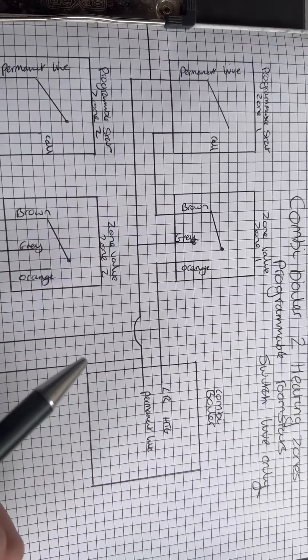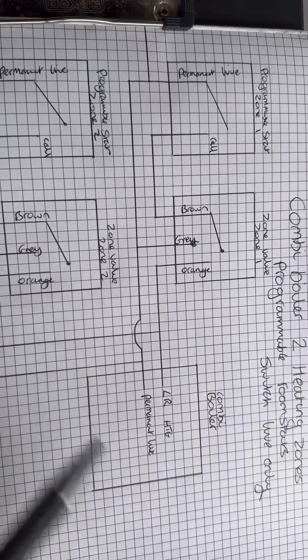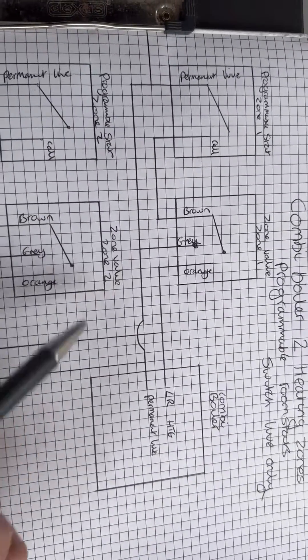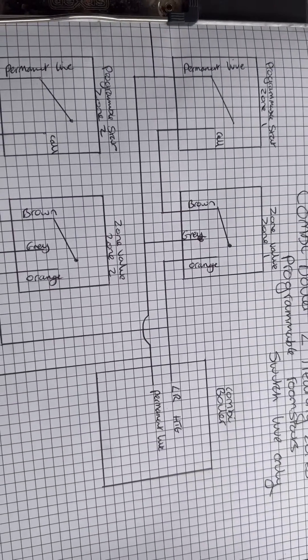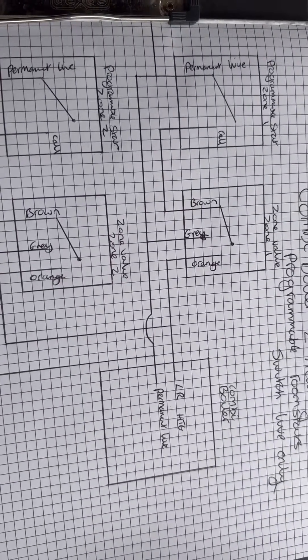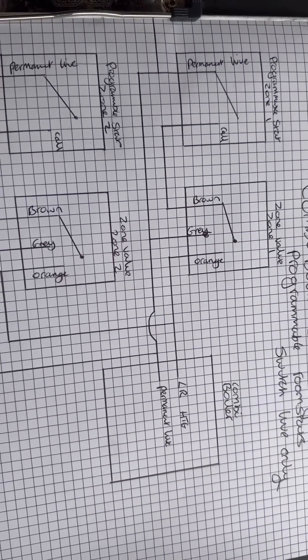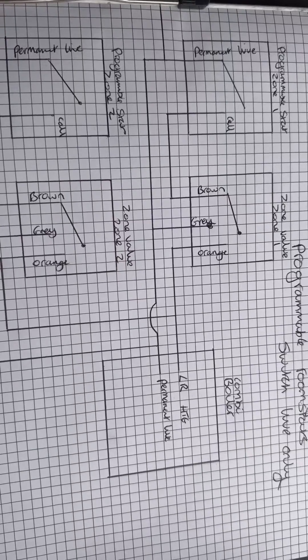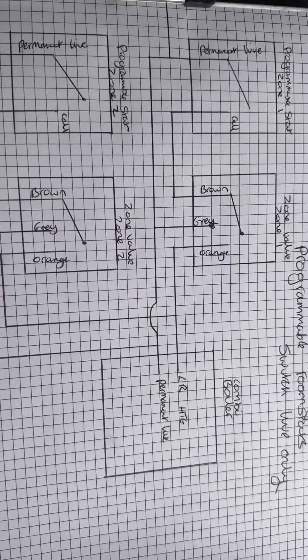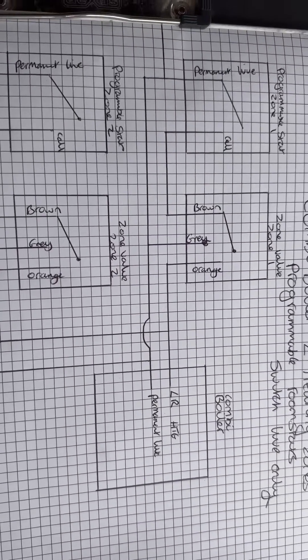But if I was getting 240 on brown, then you know it would have been the programmable room stat that was at fault. But I've just drawn it out. This will be the next chapter, well, one of the diagrams in the next chapter of the Breakdown Bible. So if you're interested in that, just give us a shout.